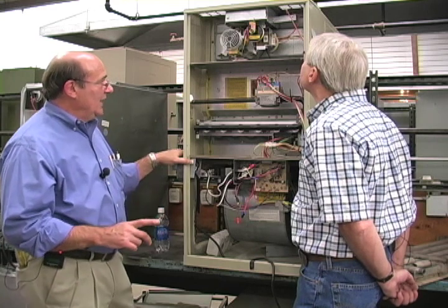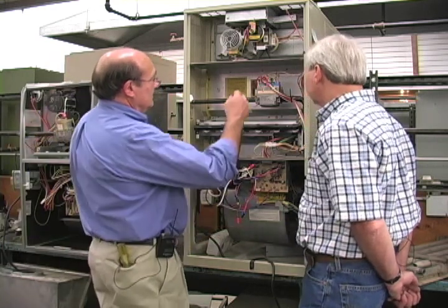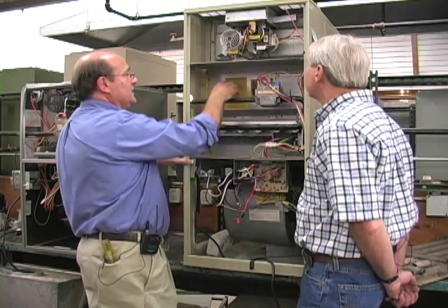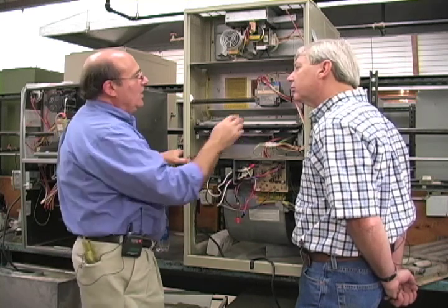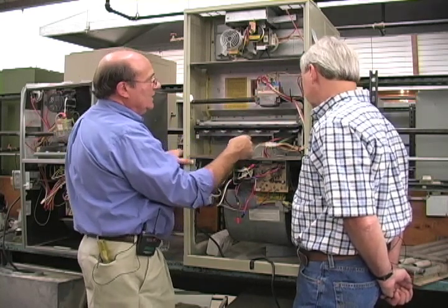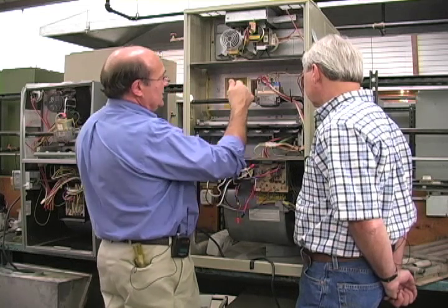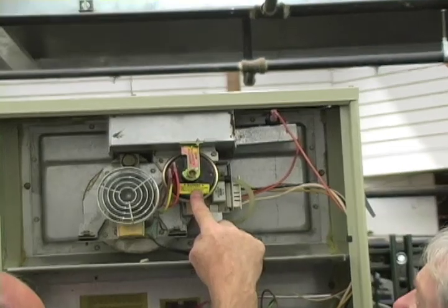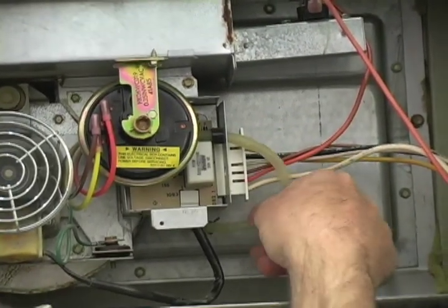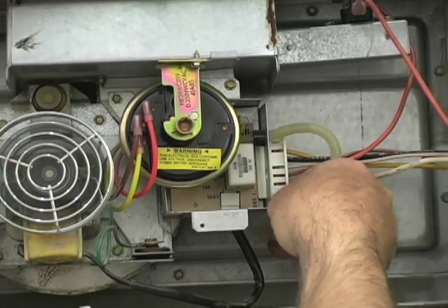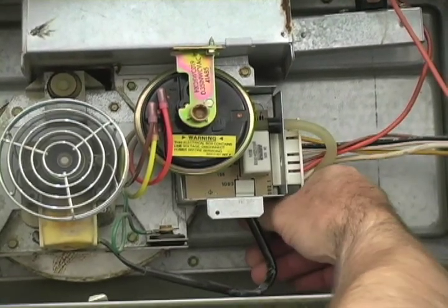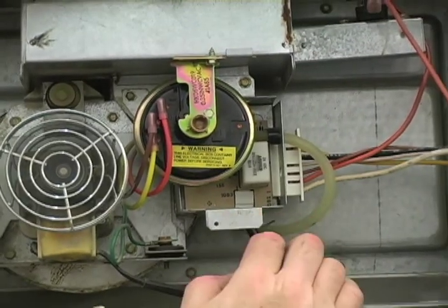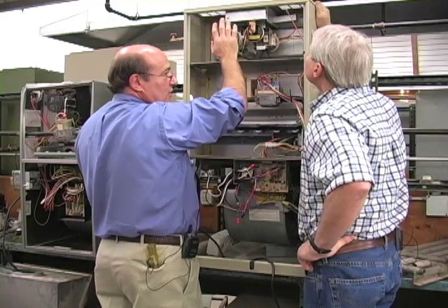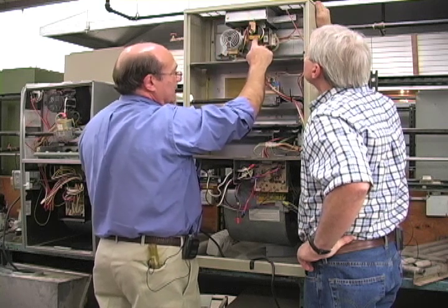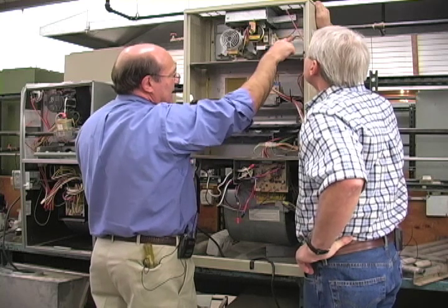One other safety feature I wanted to point out to you on this furnace is that this inducer is drawing a negative pressure through this heat exchanger. And in order to also enable the gas valve to open or the pilot valve to open, we want to prove that there's negative pressure inside this system. So this device here is a pressure switch. And it's got a tube that comes from the inside of the switch, and it's set up on a little opening in the heat exchanger there. So this tube on this pressure tap is sensing negative pressure inside that heat exchanger as this blower is inducing that negative pressure, and it's closing this switch over here. Once this switch closes, that enables the gas circuit.